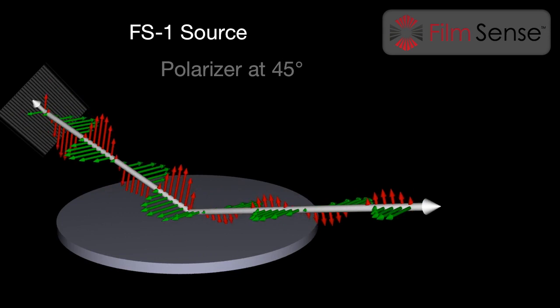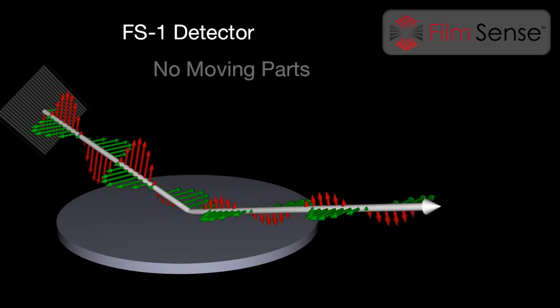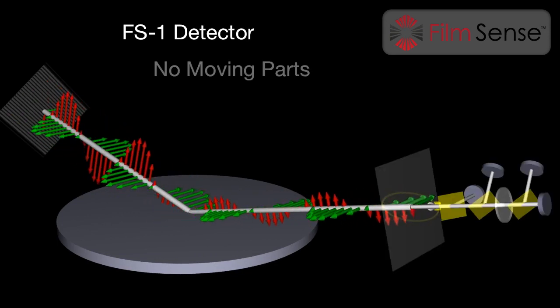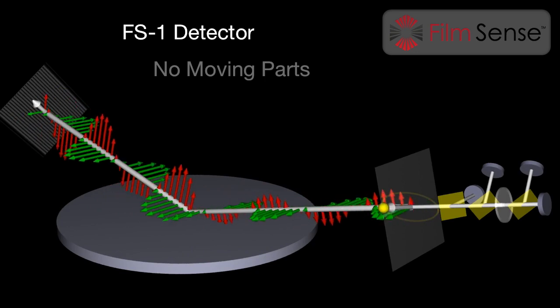The FilmSense FS1 detector unit contains a proprietary combination of beam splitters and optics, which split the beam into multiple beams and detectors, each sensitive to a different polarization component of the incoming beam. This provides fast, accurate, and reliable measurements of the ellipsometric parameters, without any moving parts.